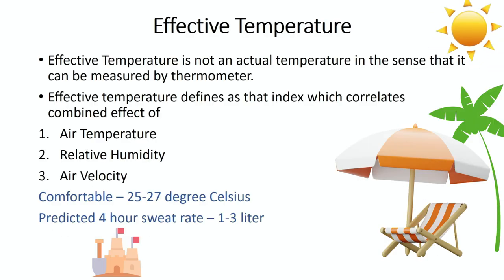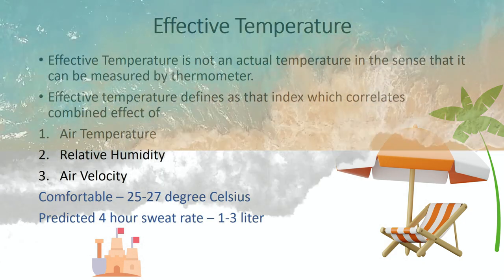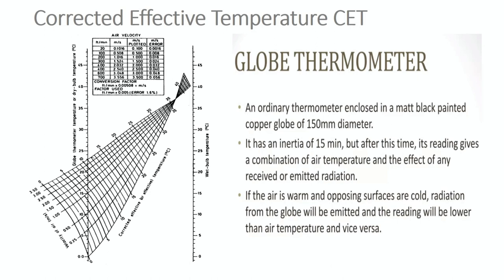Now we are moving toward effective temperature. Effective temperature is not an actual temperature that can be measured by a thermometer. It is defined as the index which correlates the combined effect of air temperature, relative humidity, and air velocity. The comfortable air temperature is 25 to 27 degrees Celsius for the average person. The corrected effective temperature includes the globe thermometer reading. In the chart, the left side shows globe thermometer temperature readings, the right side shows wet bulb temperature readings, and the middle shows air velocity cross-references, from which the corrected effective temperature is derived.